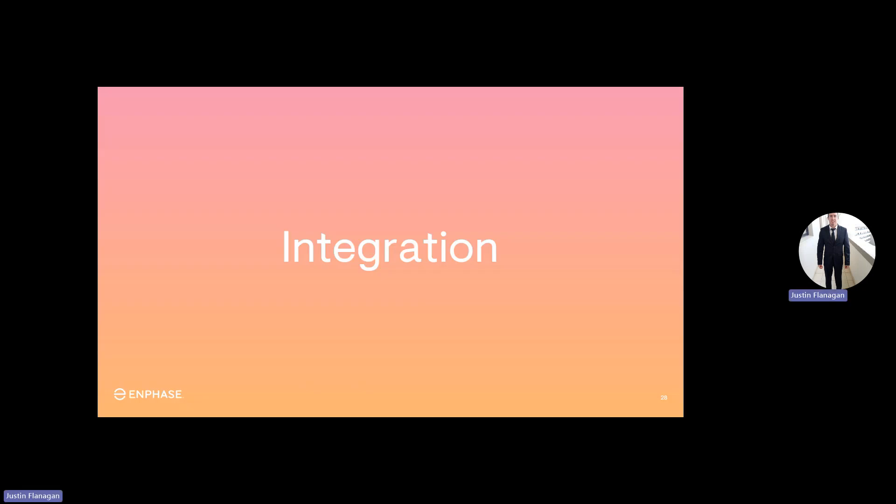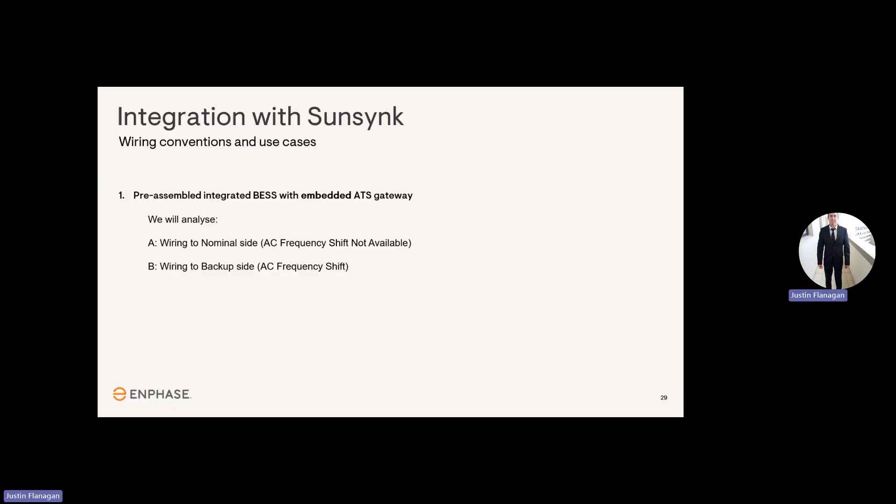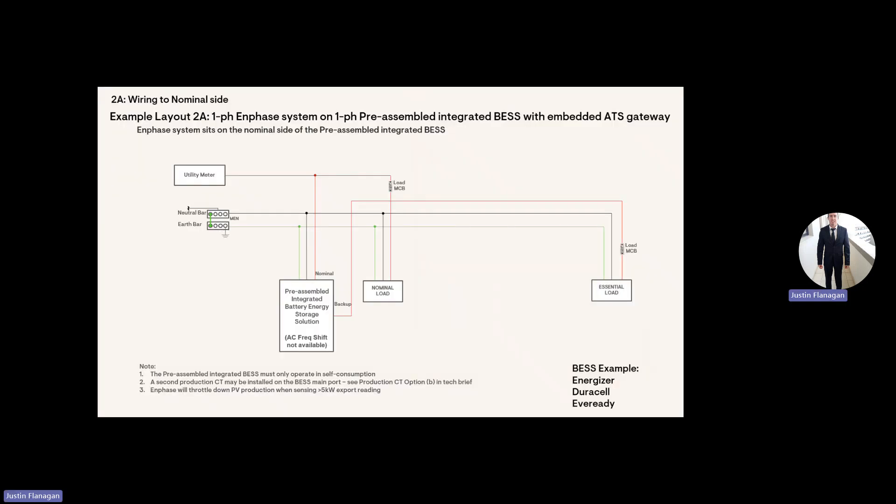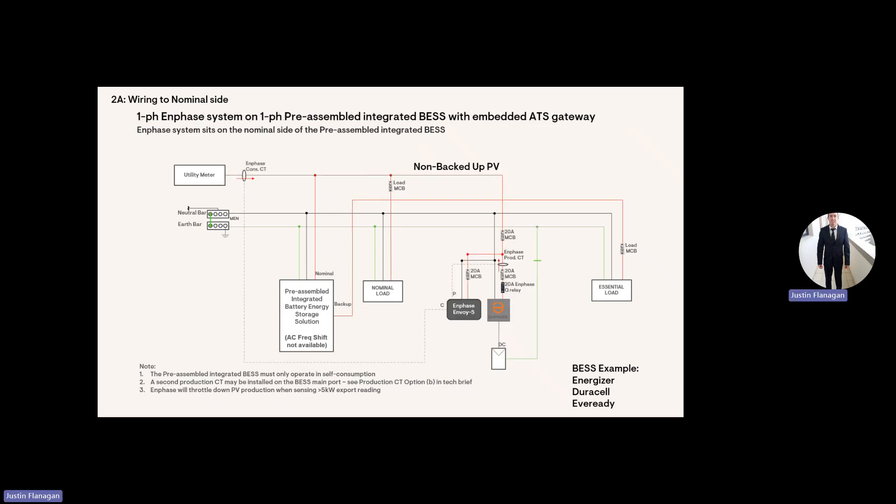Integration. So we've got to just mention integration. The first two SLDs will describe how you'll connect Enphase if the hybrid inverter cannot do frequency shift, and the second SLD will show you how you connect it onto the Sunsynk. So this is just the normal SLD with a hybrid inverter that cannot frequency shift, so the Enphase will still be connected on the nominal side of that inverter. So that means when there is a grid outage, Enphase will switch off.